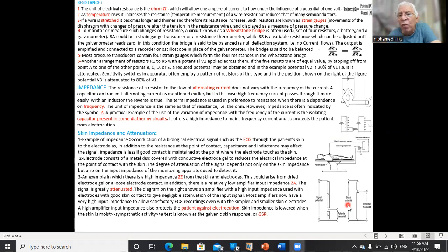and it will attenuate the signal. Of course, the equipment which reads the ECG also has a resistance. We call it Z apparatus. It is better for me to increase the impedance of the apparatus at the expense of the electrodes to improve the signal and lessen the harmful electrical shock which can happen.